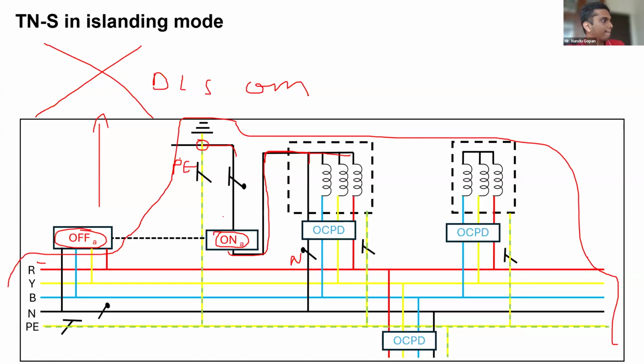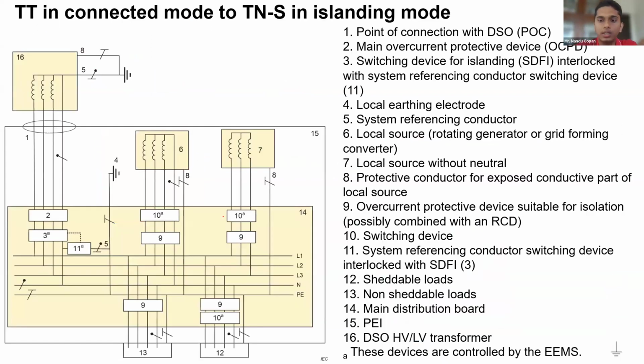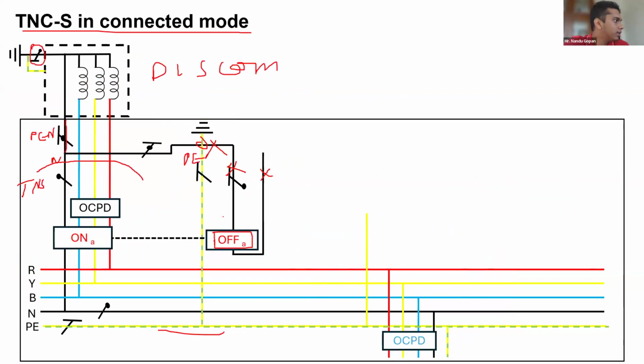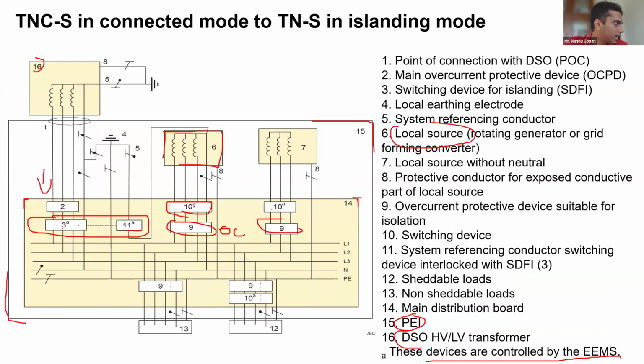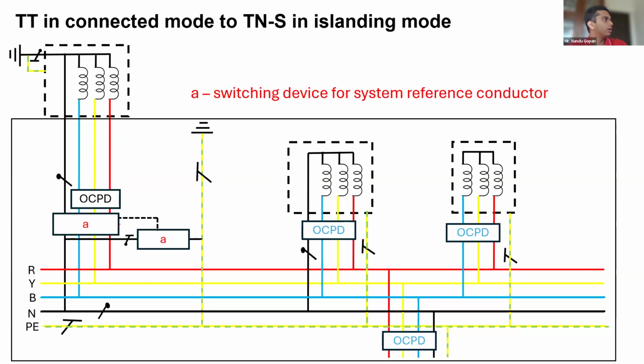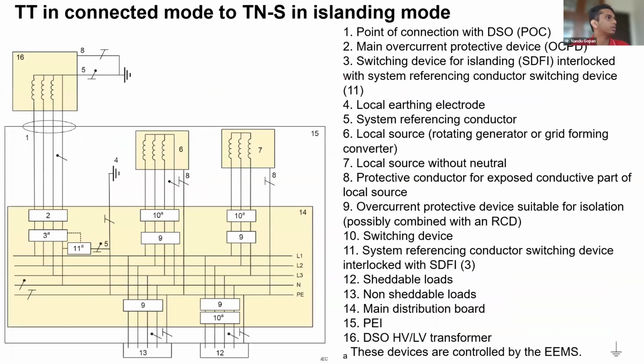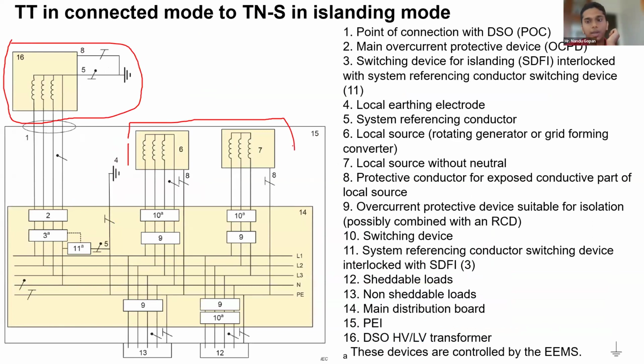Now, what happens if, so this is how it is, the system referencing has been done. So mostly I'll just brief it a little shortly. This interlock, which is happening between 3 and 11, will decide on how the system referencing is done in this connected and islanding mode. Now, one second. Okay. So what happens if there is a TT system which is coming from here? The discom is providing a TT system, and in islanding mode this should work in TNS supply. Then how does that work? So I'll be explaining that.